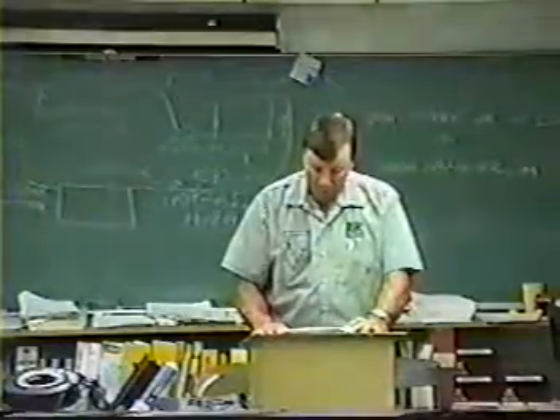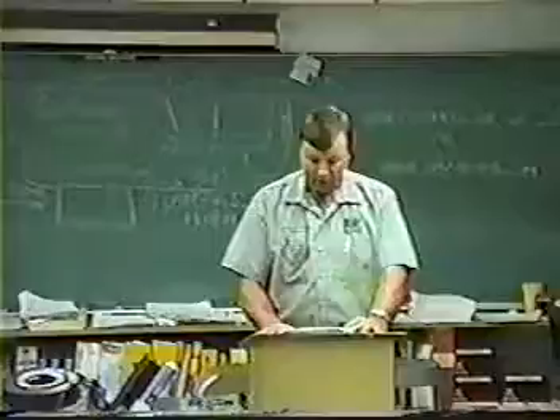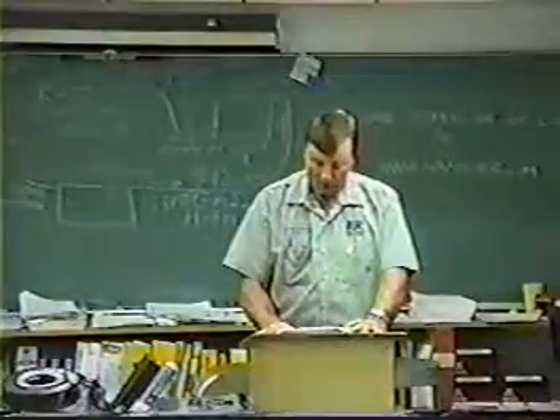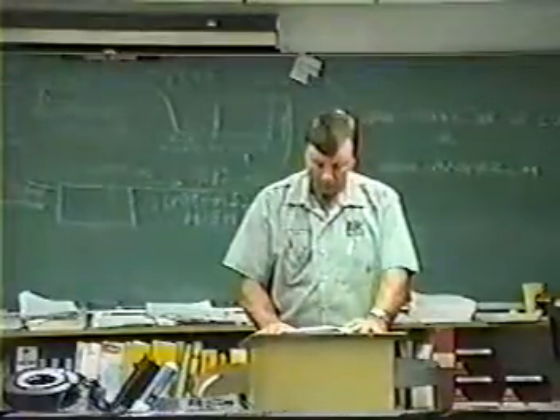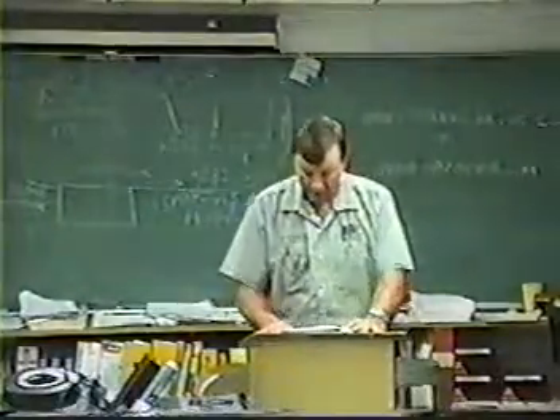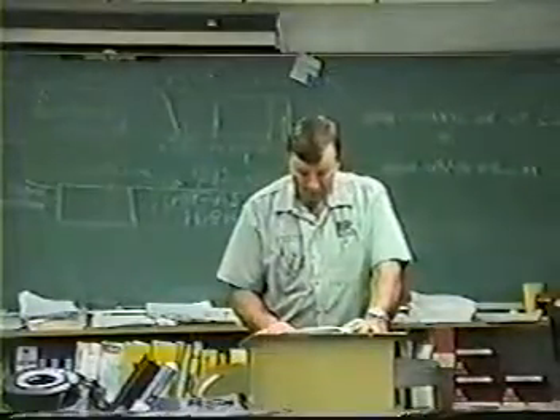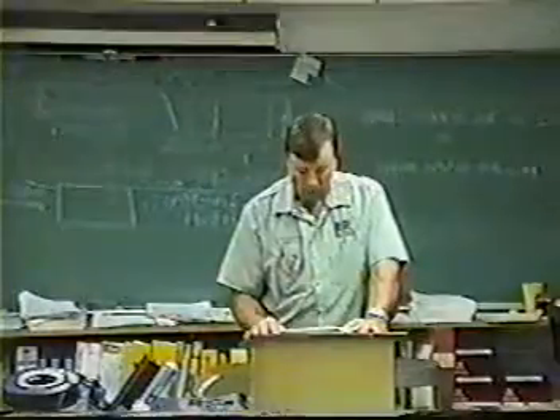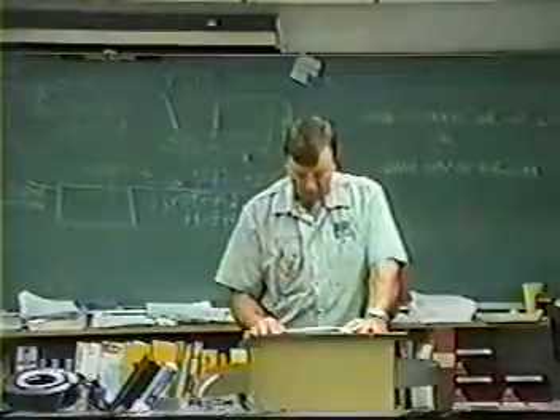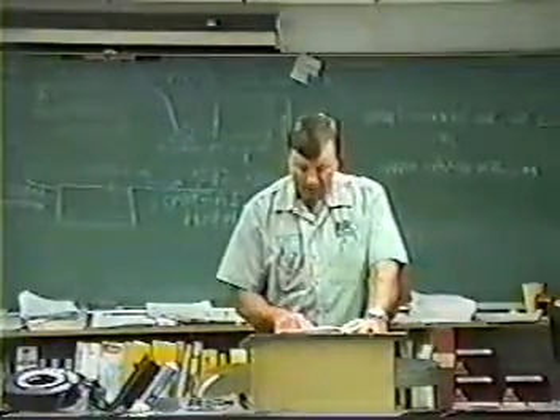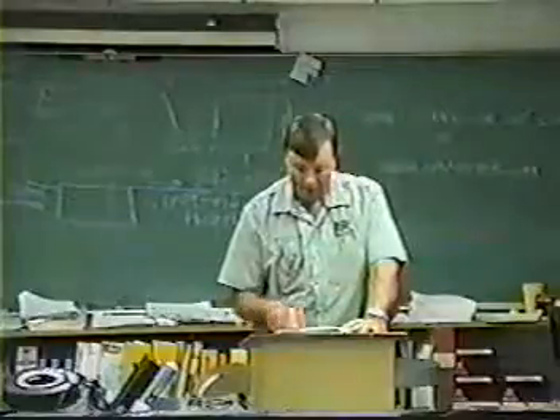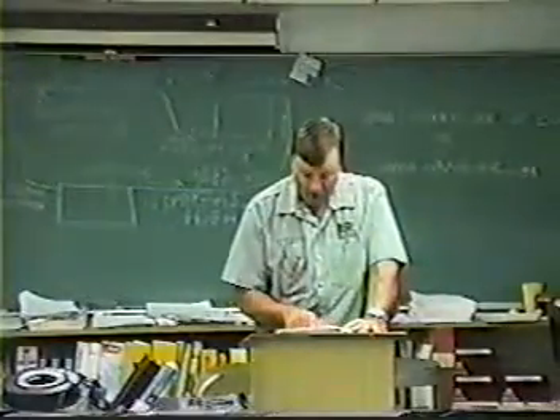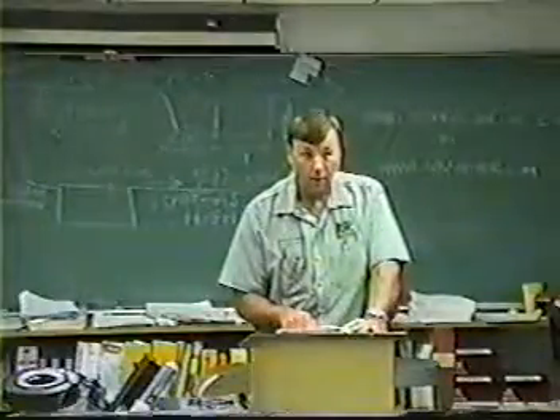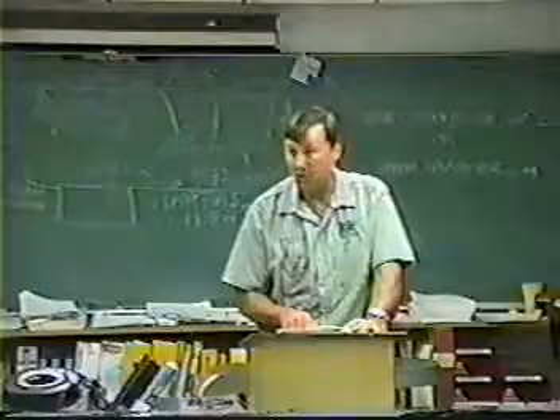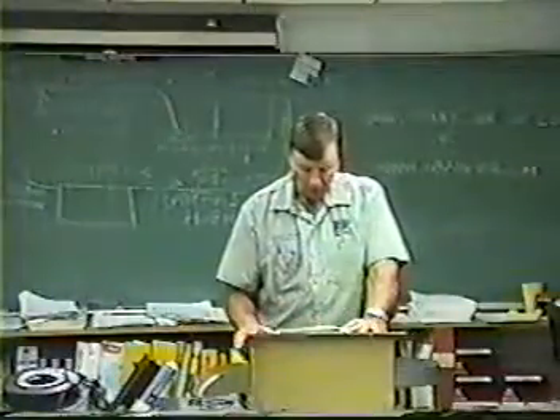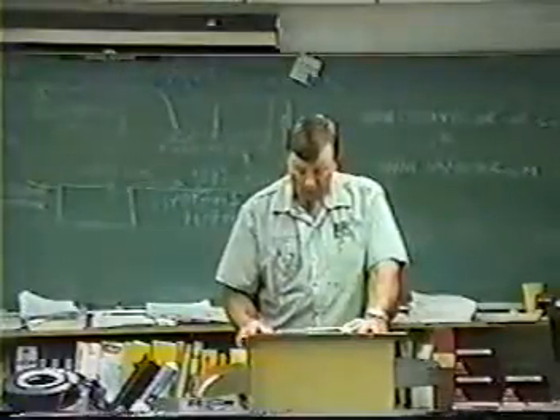After reaching the appropriate recovery vacuum, the technician should wait a few minutes to see if the system pressure rises. Pressure may increase as refrigerant is released from the compressor oil. If system pressure increases, recovery must be repeated. That's a test question. When leaks in an appliance make evacuation to the prescribed level impossible, the appliance may be evacuated to 0. That's a test question too. Maybe as low as it can go. If it's impossible, maybe it has so many leaks in it, it won't go any lower than that. The technician must isolate a parallel compressor system in order to recover refrigerant.